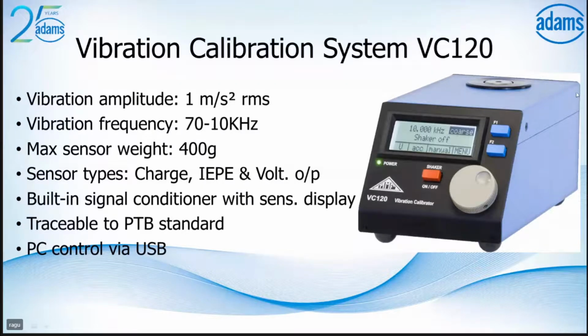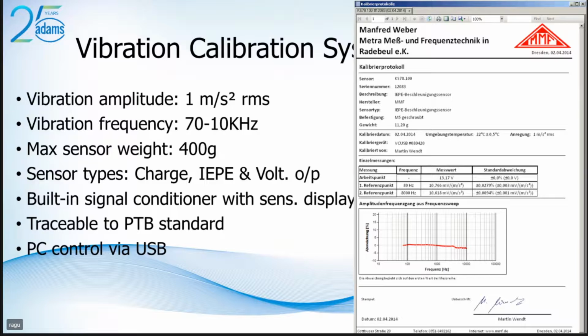So the sensor will be connected at the rear end of the VC120 system, and it displays the sensitivity. This contains all the signal conditioning, charge and IEP. So it is a beautiful small tabletop that allows you to calibrate your sensor in the complete frequency range of 70 hertz to 10 kilohertz. It is also complemented by software. At the end of calibration, you also get a beautiful report from Metra.